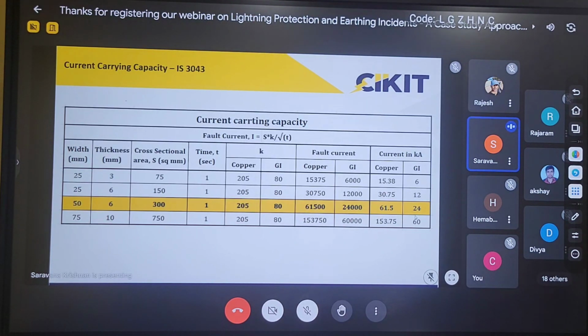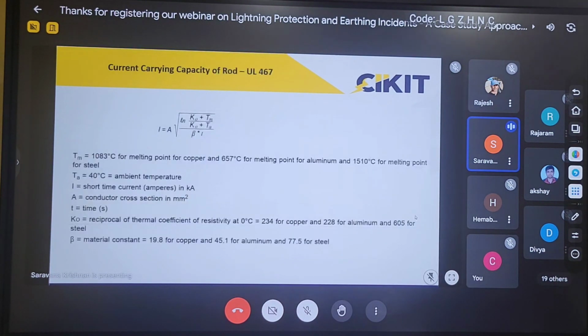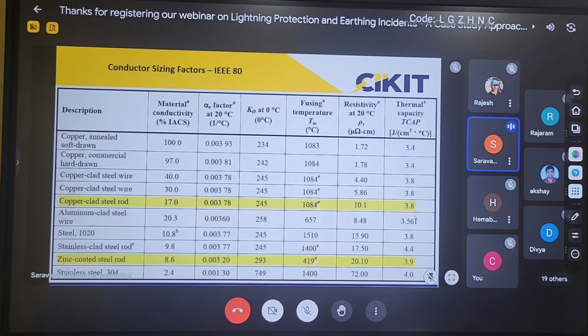But in IS 3043, they have provided the constants for everything related to steel. If I take GI, it will be hard galvanized steel, where the coating of zinc comes into the picture. In IS 3043, they have not provided much detail about this zinc coating and its effect. So we have referred to another standard, UL 467, and IEEE 80 for calculating the current carrying capacity of coated materials. IEEE 80 has mentioned the different parameters related to the current carrying capacity of coated materials. These are the parameters provided by IEEE 80 related to coated material.